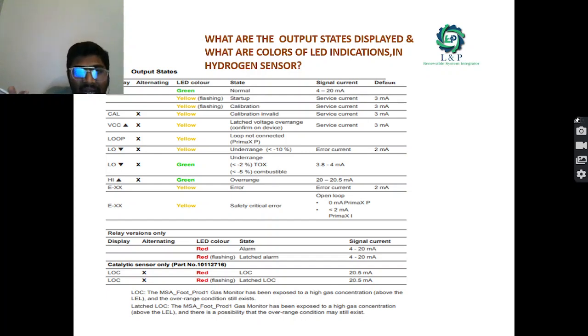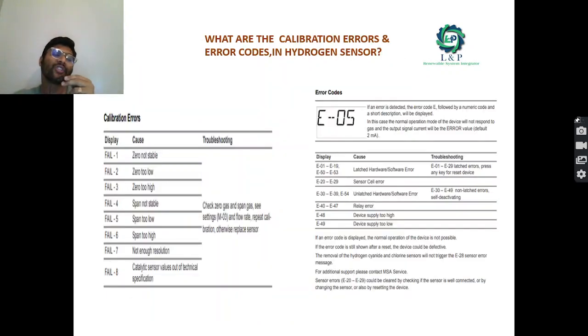And if the red LEDs keep on flashing, it means the alarm is latched. If you want the catalytic sensor types, the output signal range will differ. And what are the different calibration errors and error codes inside the sensor? If the display shows fail 1, it is zero not stable. If it is fail 2, it is too low. If it is fail 3, it is too high. If it is fail 4, the span is not stable. And if it is showing fail 6, the span is too high.